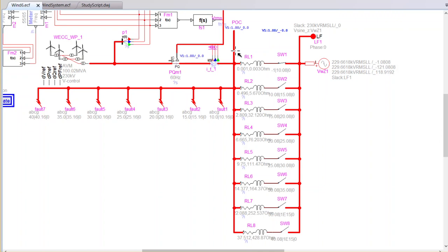So here I've changed this voltage source, so it's got essentially zero impedance. It's just an ideal voltage source, and I put in a very small reactance here of 0.003 ohms. So this is the strongest the grid can be. Now we still have inductive elements inside the plant. In here, we've got the park transformer and the inverter transformers. So that adds significant inductance, so that from the standpoint of the voltage source converter, there's still a significant short circuit ratio.